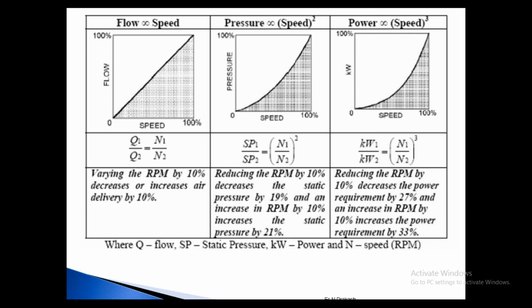If you reduce the speed, you have to see how it is going to help us. When you reduce the speed of the fan within the multi-fan system, ensure that all the fans are evenly done. One fan may be set this way and run for 2-3 months, while the other fan works at the correct RPM. That is also a problem. Also, in the axial flow fan design, there is a blade angle. The higher the blade angle, the more air it cuts and the more pressure it creates. If you reduce the blade angle, there is free flow of air, and because of that there is low power. So blade angle as well as RPM and the number of blades all matter for the power cost, based on the original selection.